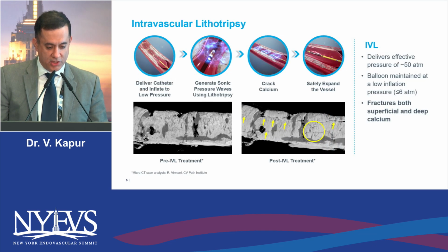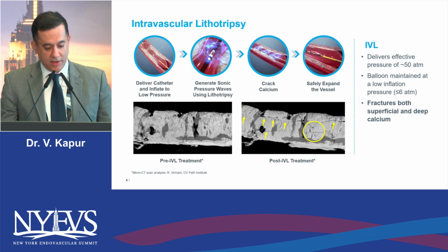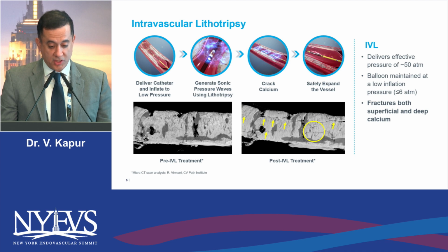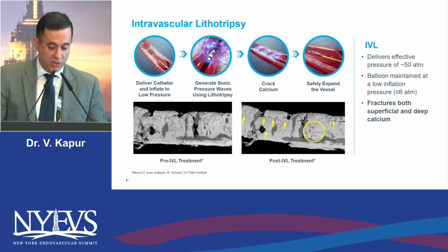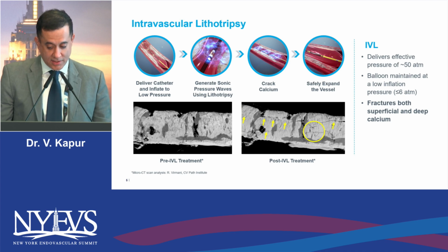So the mechanism essentially involves delivering a catheter and inflating it with low pressures. The low pressure technically generates an effective pressure of 50 atmospheres by these sonic beams, which are in these emitters, which then crack the calcium, and then it expands the vessel.